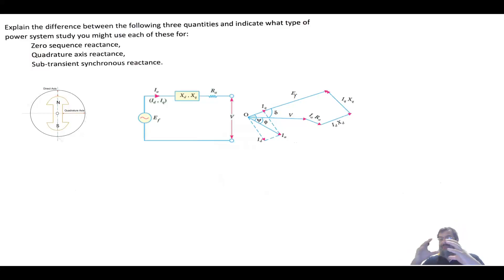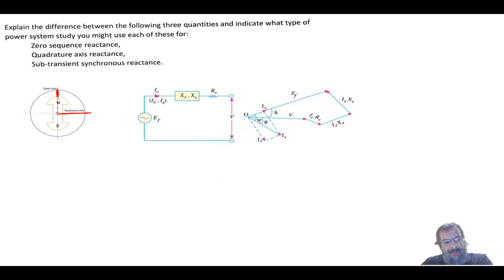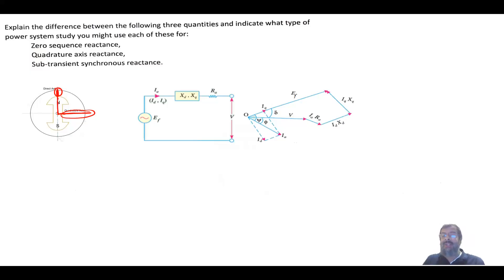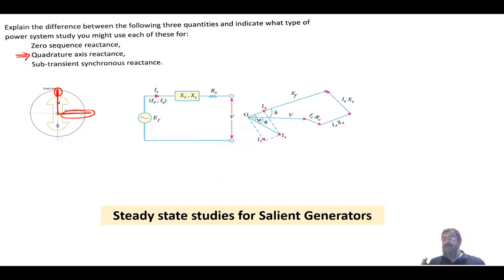The second type is the salient pole generator. In the salient pole structure, there are two different air gap distances: one along the direct axis and one along the quadrature axis, which is 90 degrees away. One gap is small and one is large. Because of this, we decompose the reactance into two separate reactances: the direct axis reactance xd and the quadrature axis reactance xq. This model is used in steady-state studies for salient pole generators.